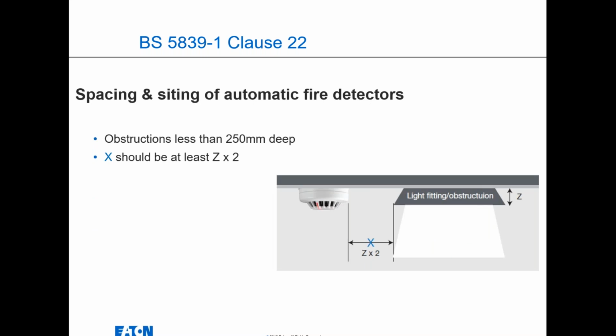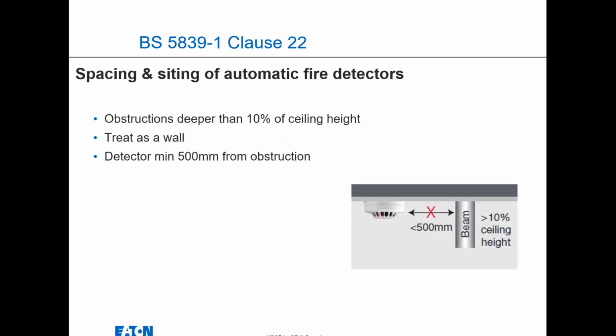The spacing and siting of automatic fire detectors, again, you need to be thinking about obstructions that are 250 mil deep, because that could potentially mean you've got to put one on either side. So if they are more than 10% of the ceiling height, you need to treat them as a wall, and then make sure the detector is not closer than 500 mil. So if you've got a room with a big beam in the middle of it, you might have to put 2 detectors in it to meet the standards.